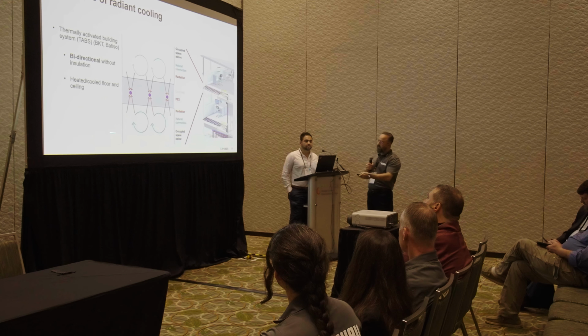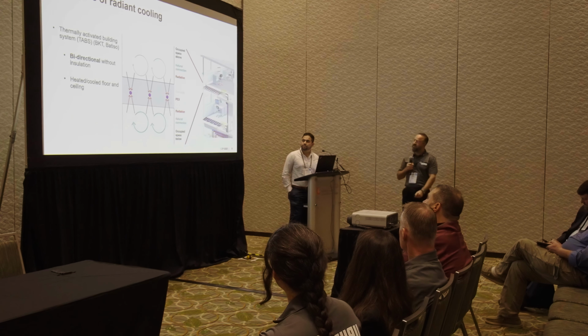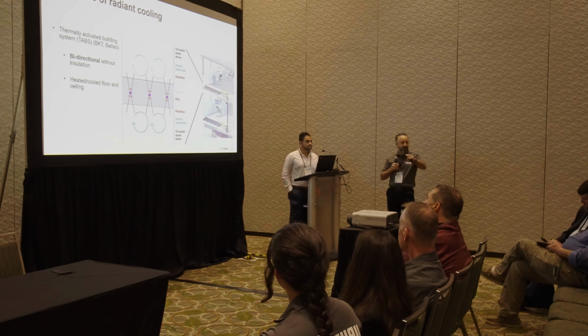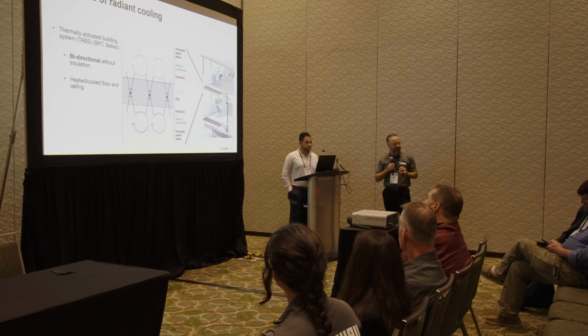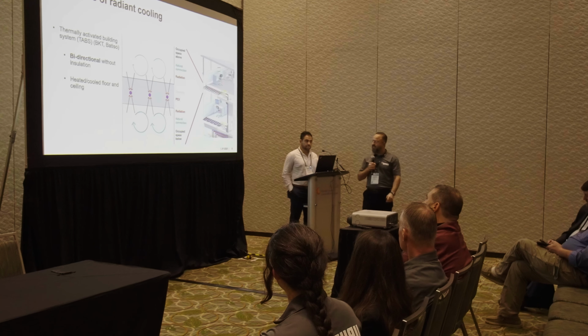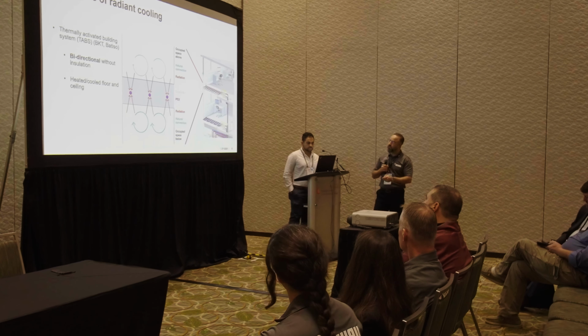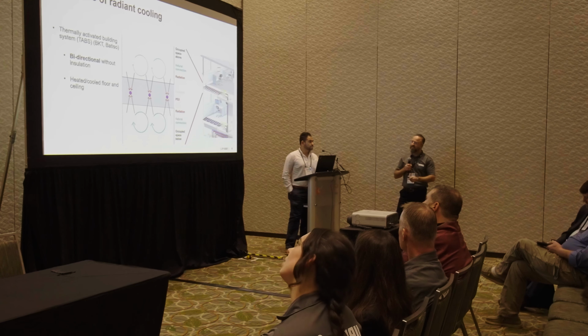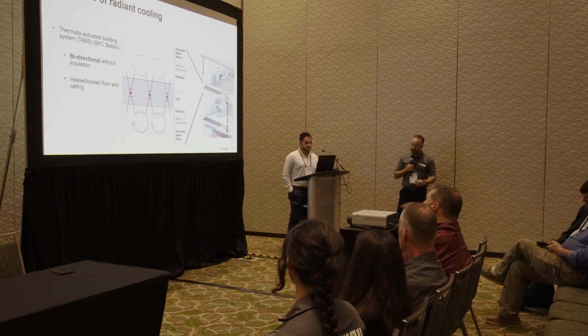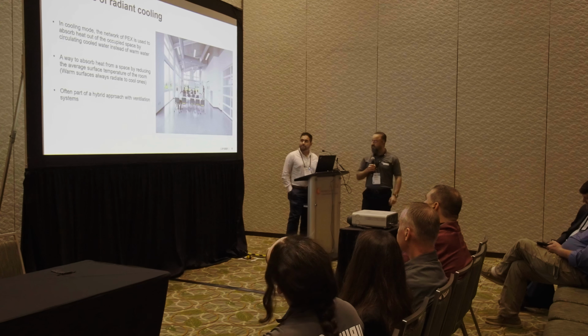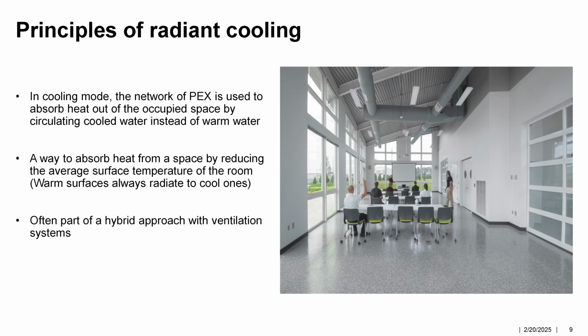But the reason that we highlighted this section is when it acts as a ceiling system, it takes advantage of natural convection, because the air comes in contact with the chilled ceiling, and by getting a little bit colder, it drops down. So that helps with the performance as opposed to the top one. If it's in a radiant heating mode, it helps a lot with the natural convection. So these are the two ways that we do it. As I said again, more than 95% is unidirectional heat transfer to the space.